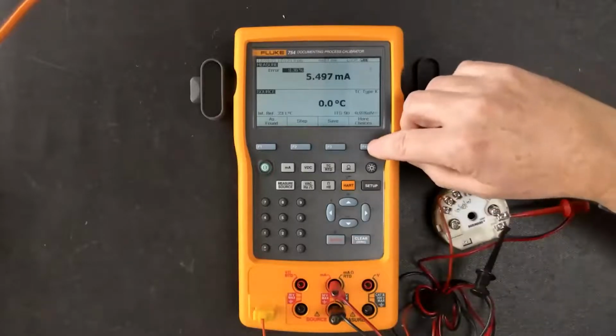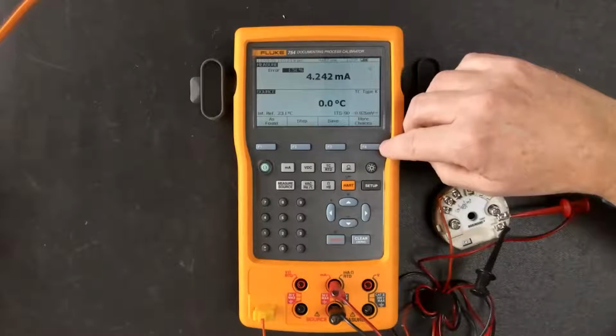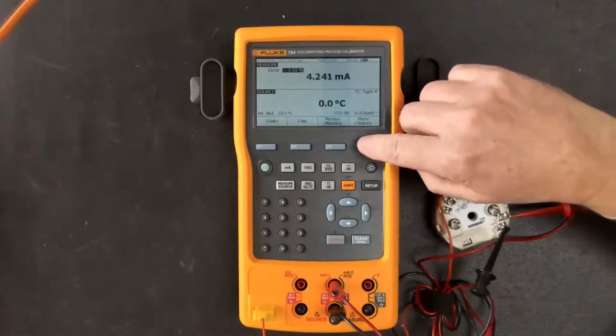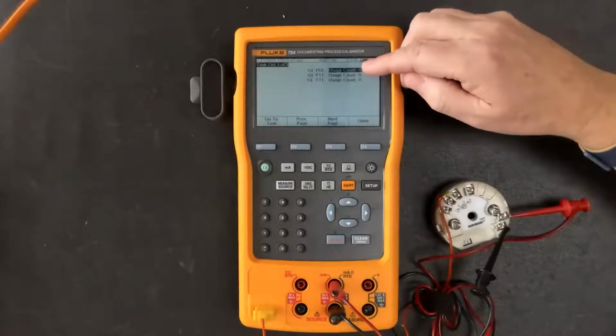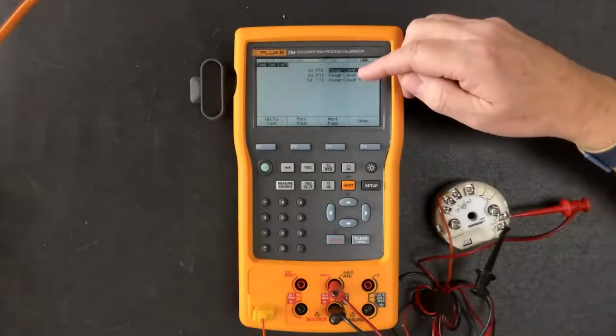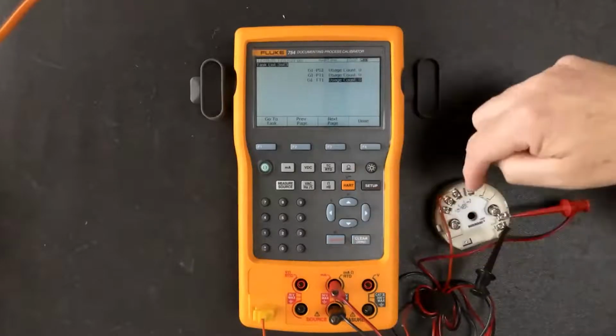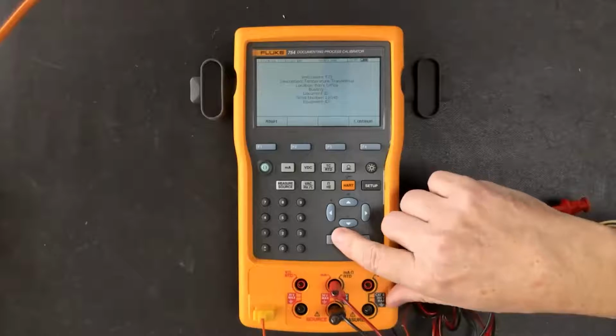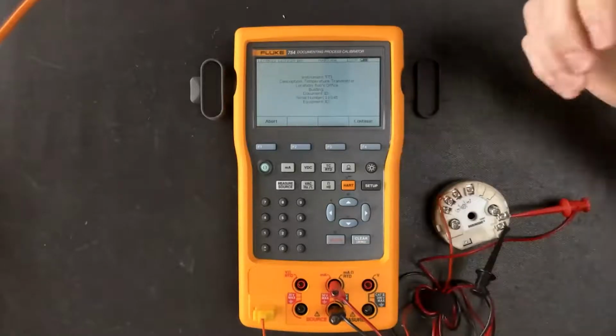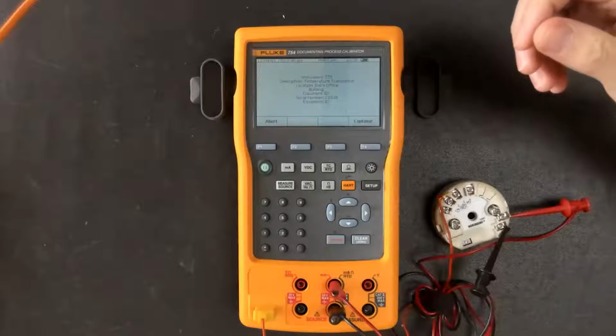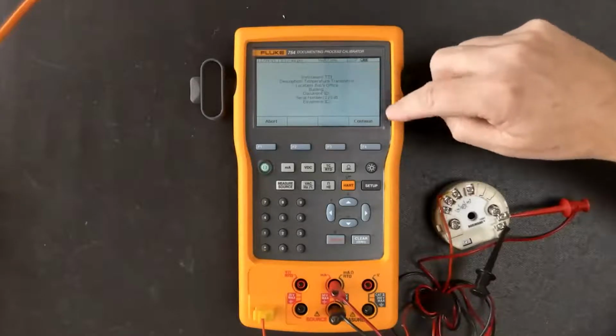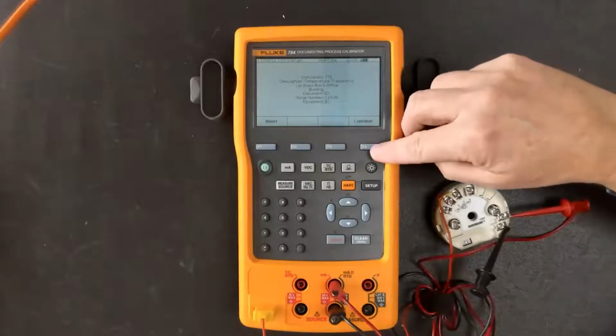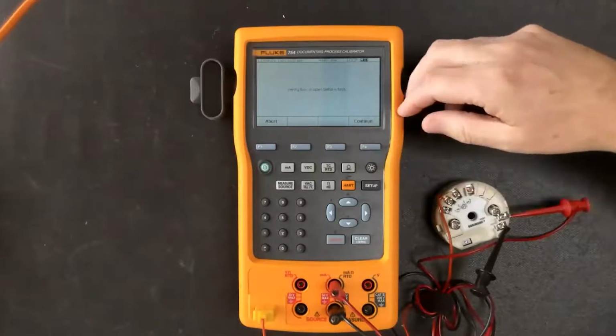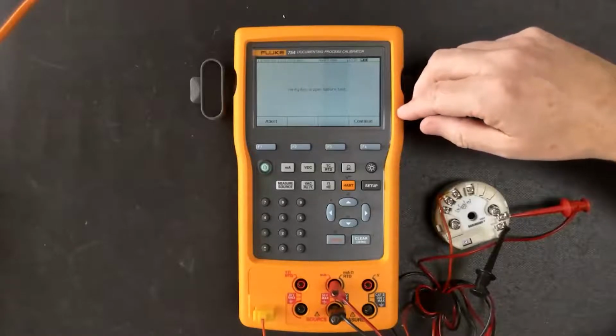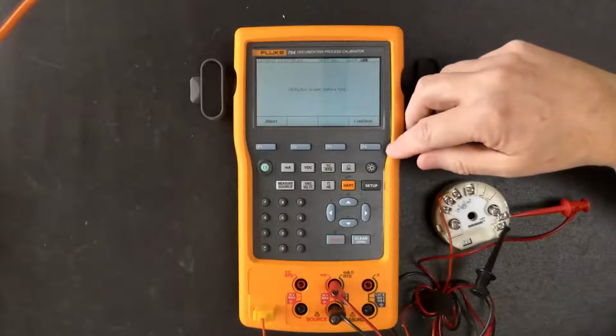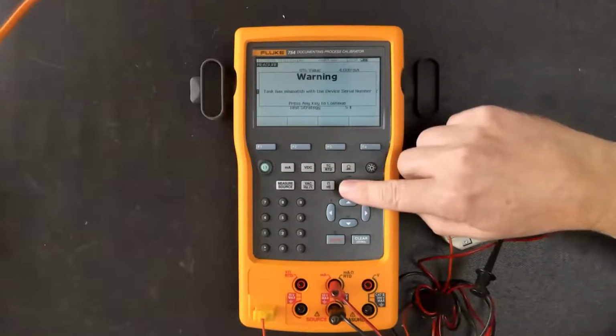From this screen now, we have already downloaded some tasks from ProCal. So if I go to more choices and hit tasks, you'll see I've got a few tasks that I've downloaded, and you'll notice down here TT1, and that's this guy here. So I can bring it up, and you'll notice you can program into it from the software. You can get the information about the device so the technician knows where things are located. Also, you can send a message to the technician from ProCal. In this case, I just said verify the box is open before testing, and then we'll continue.